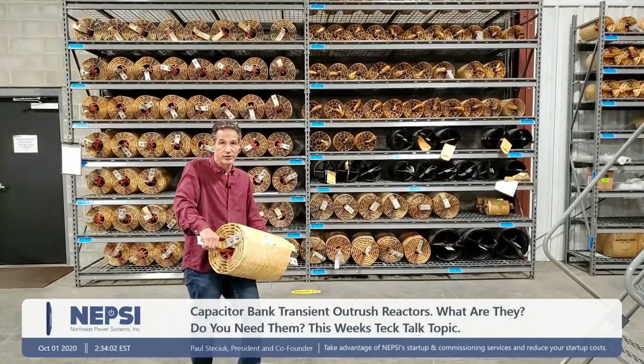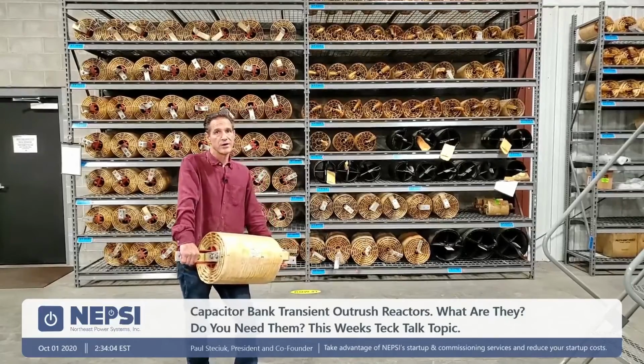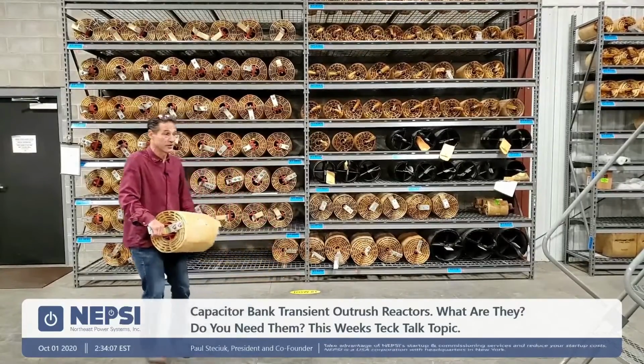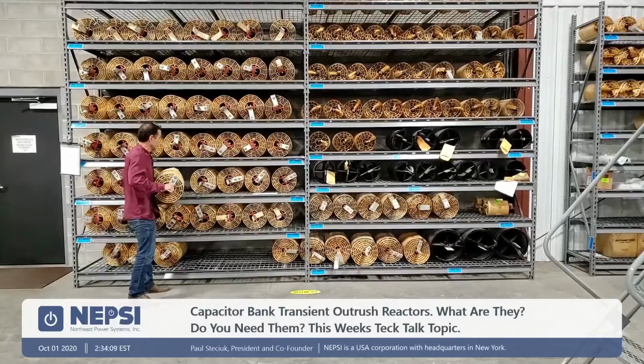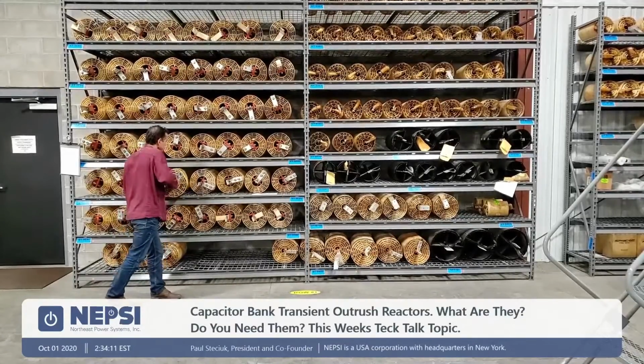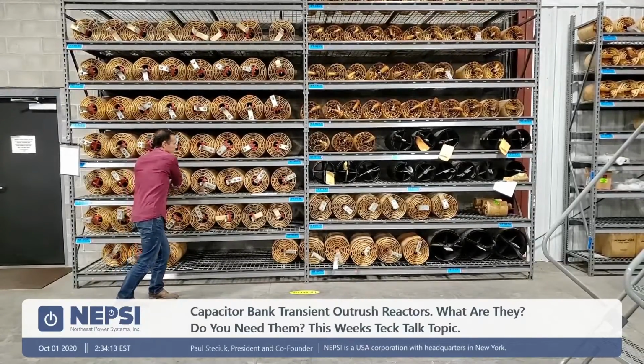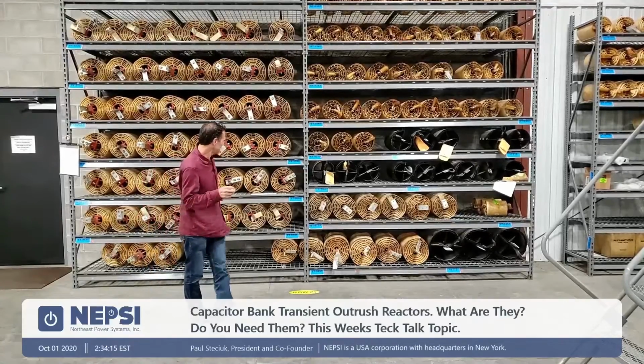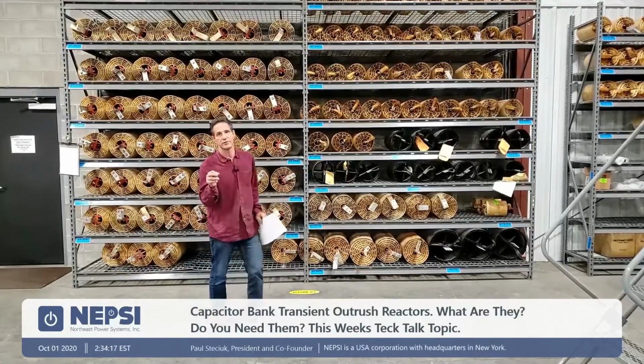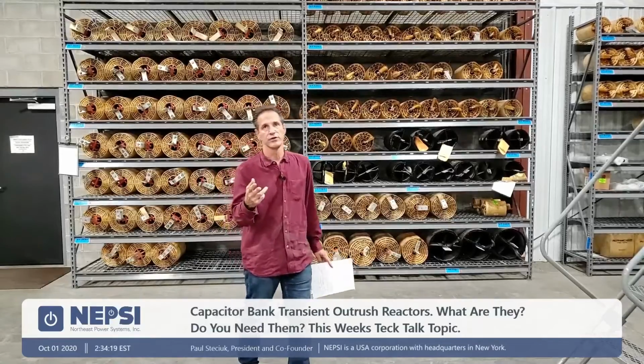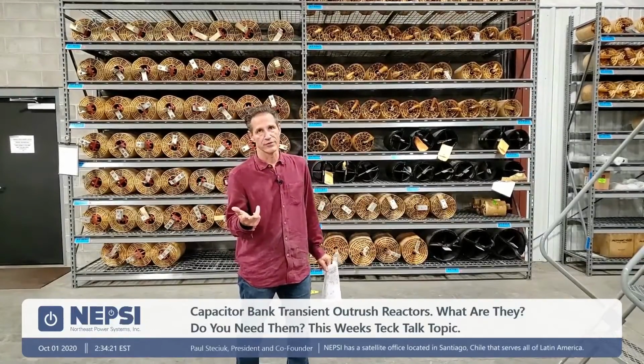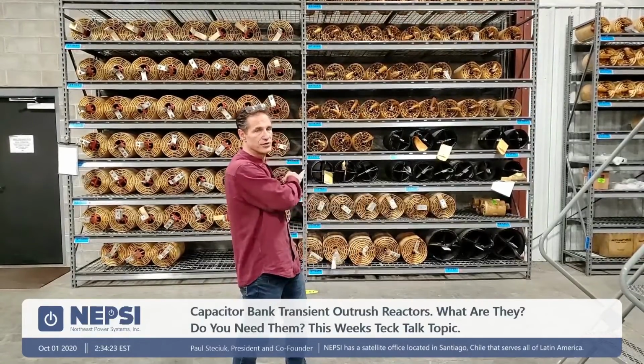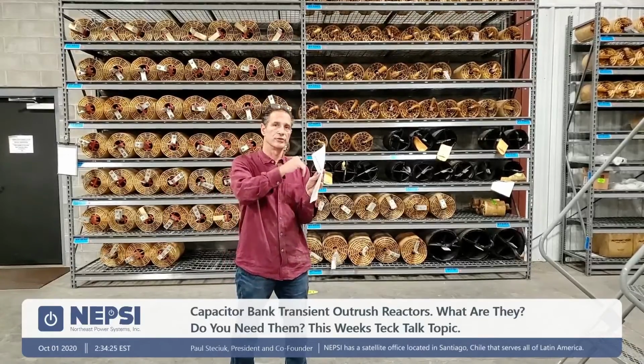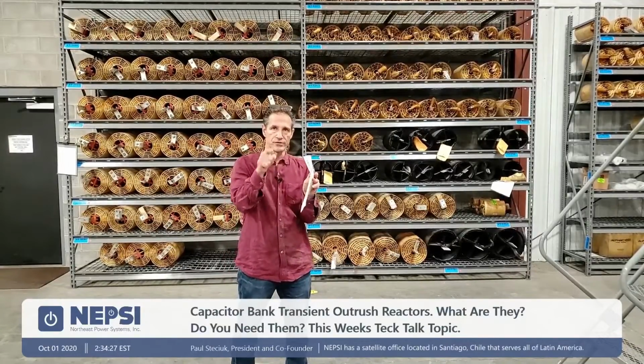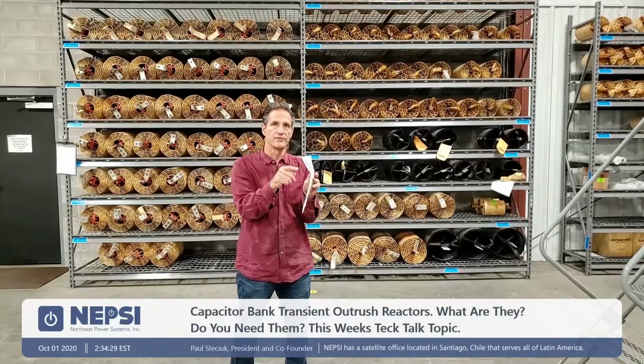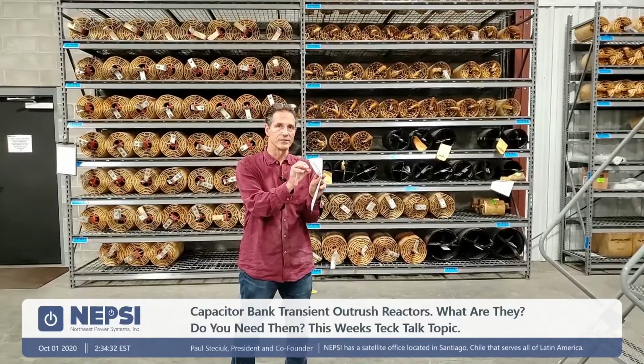So 47 microhenries. When we're talking about outrush reactors, let me put this down, it's heavy. When we're talking about outrush reactors, typically we're talking about inductance values in the order of, say, 200 to 300 microhenries. So transient inrush reactors will reduce the back-to-back switching transients within the bank for the switching device within the bank.